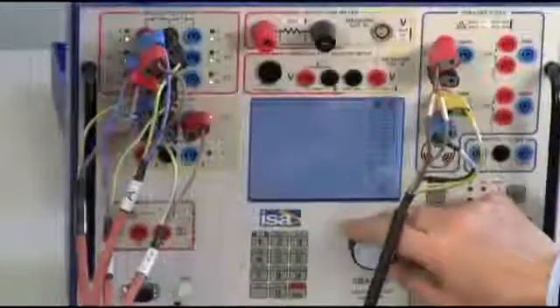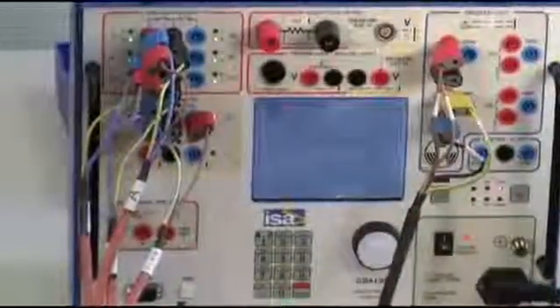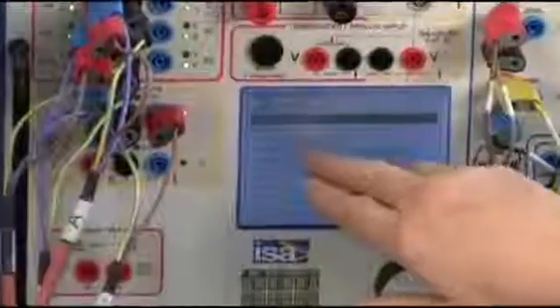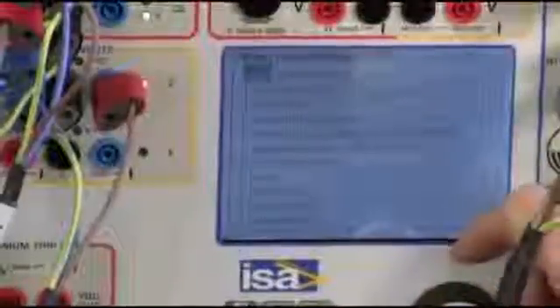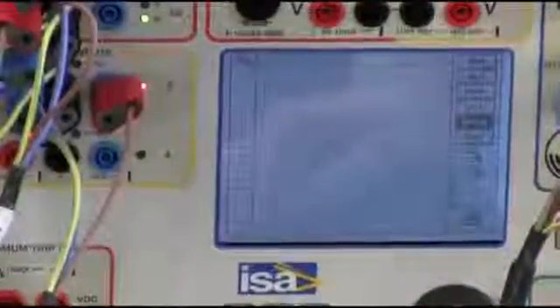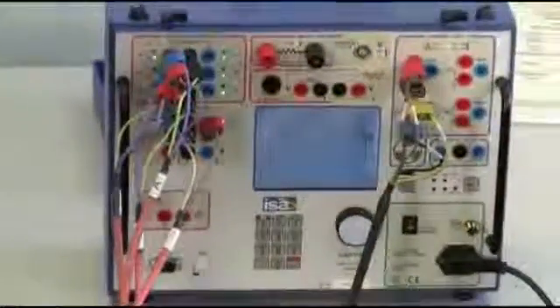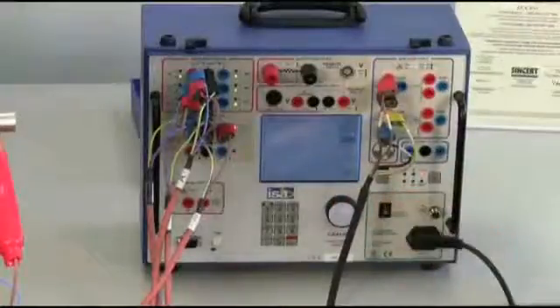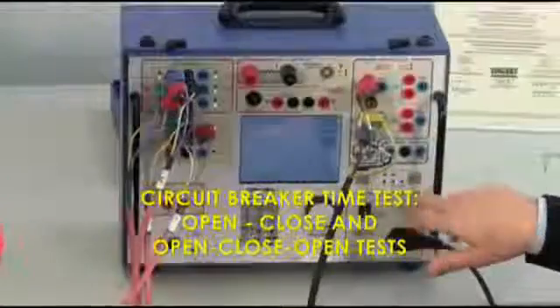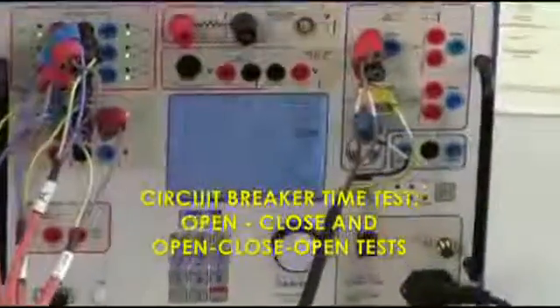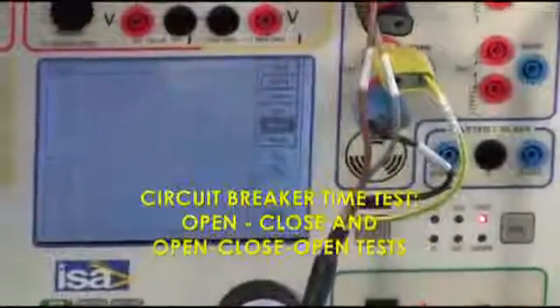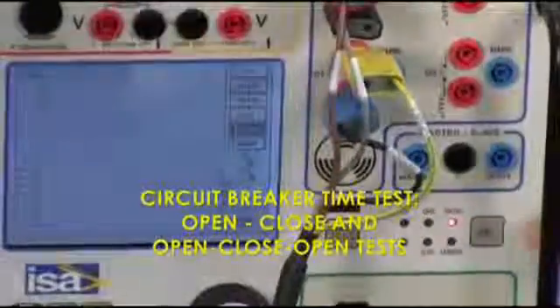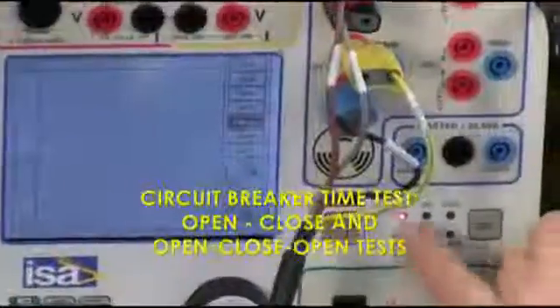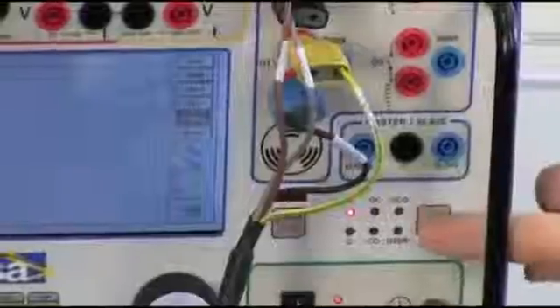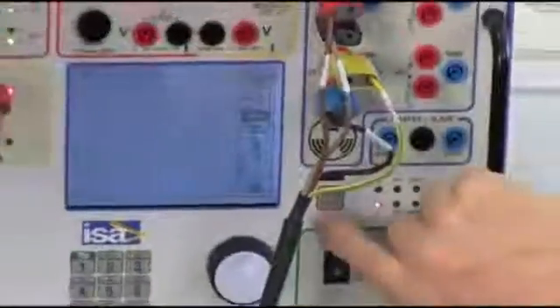Once you do it, you can go to the menu if you want, and then start setting up trigger option, test option, recording options, and so on. I want to operate immediately without losing too much time, and what do I want to do? The circuit breaker is open, okay? So the first operation will be close it, and I can record the timing during the close. And next I will go to open, close, open. That is the most severe sequence that the circuit breaker must withstand. Setting the test is immediately performed by pushing here this button. Now it is set on open, but it is already open, so I go to close. Once I have done it, I just press start.